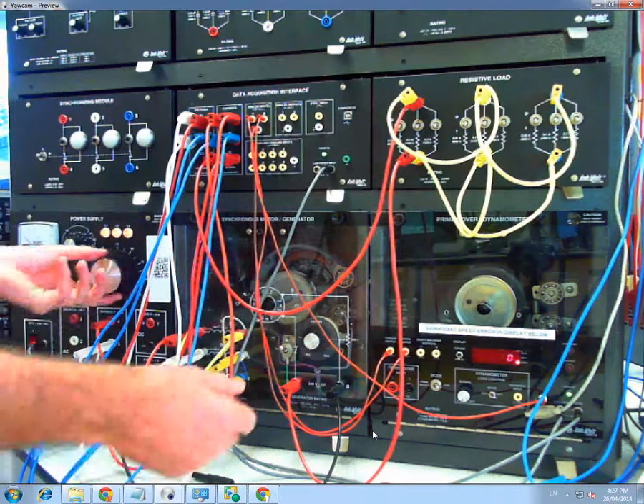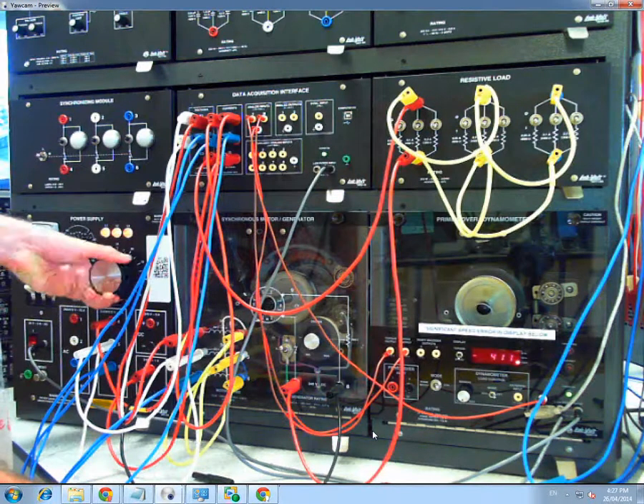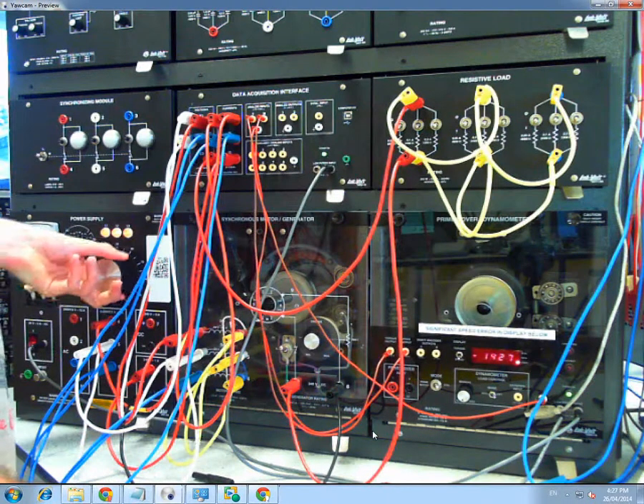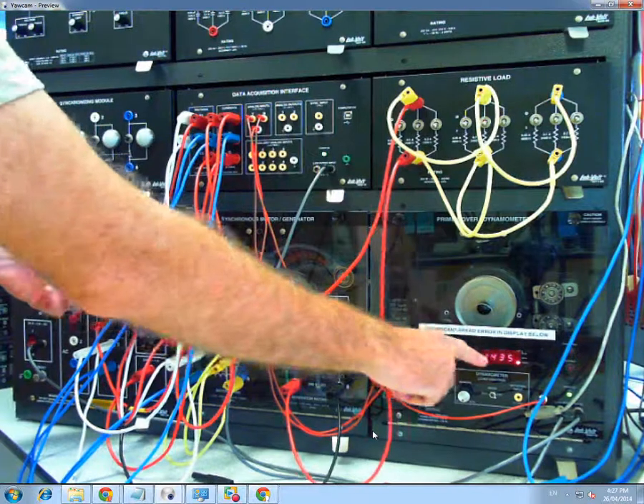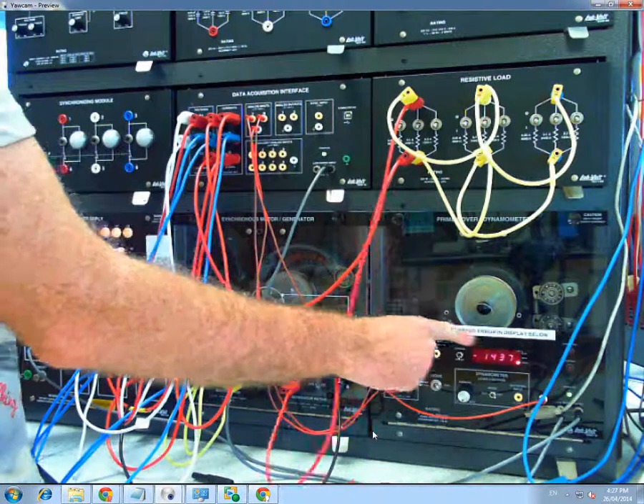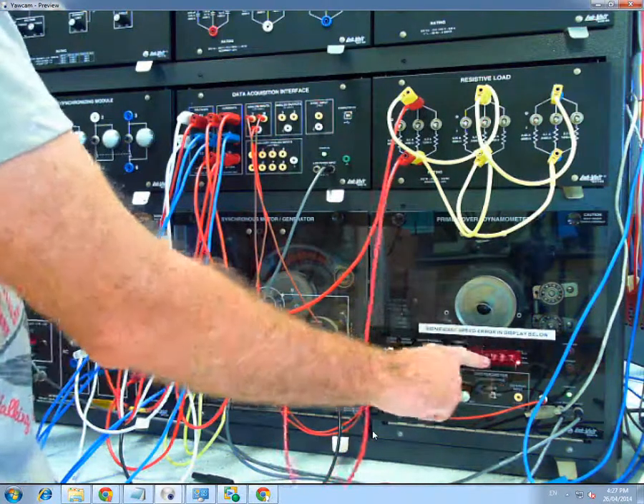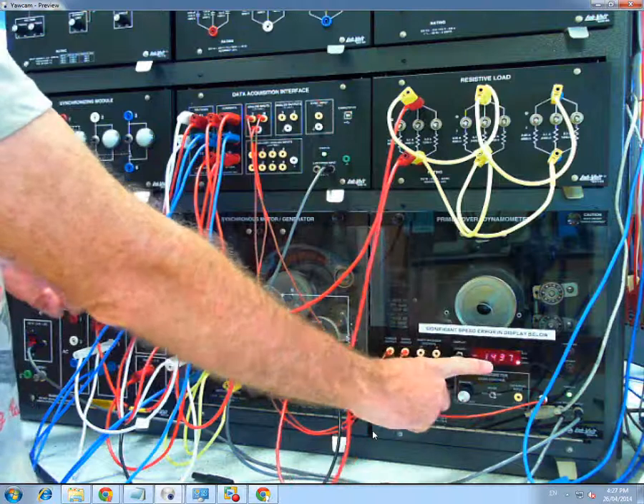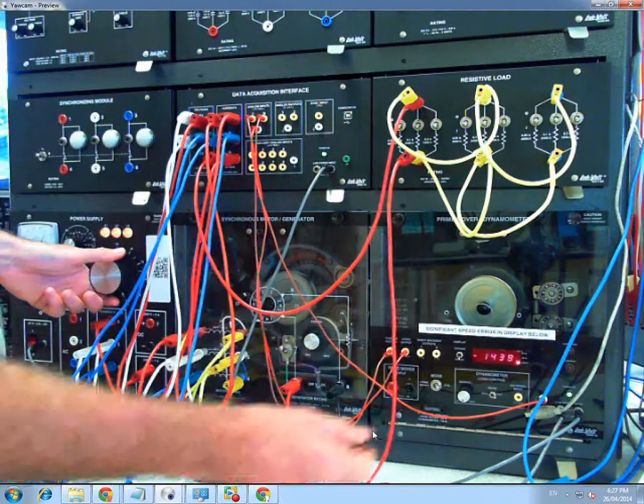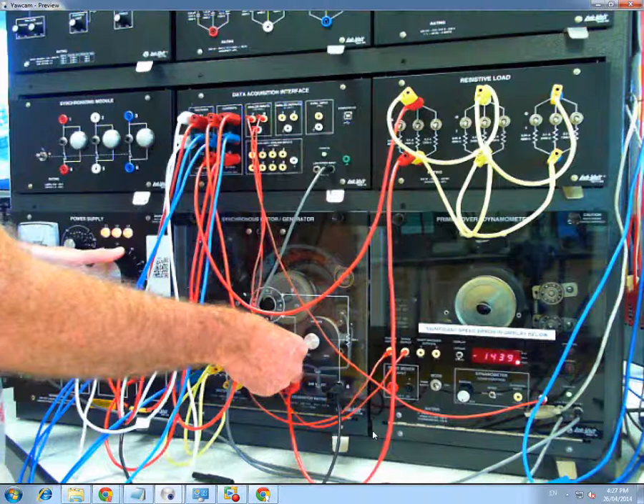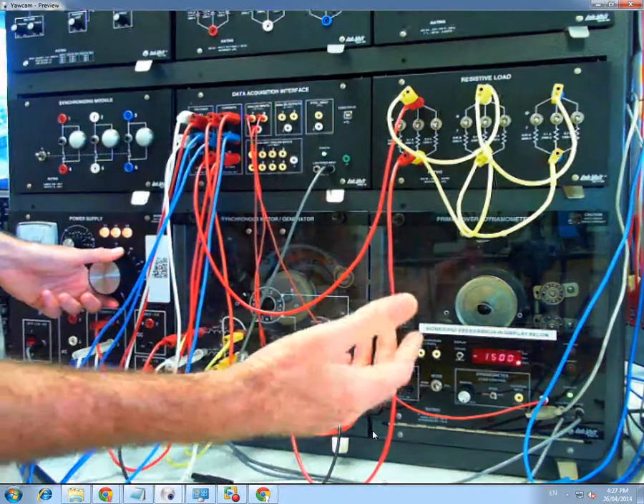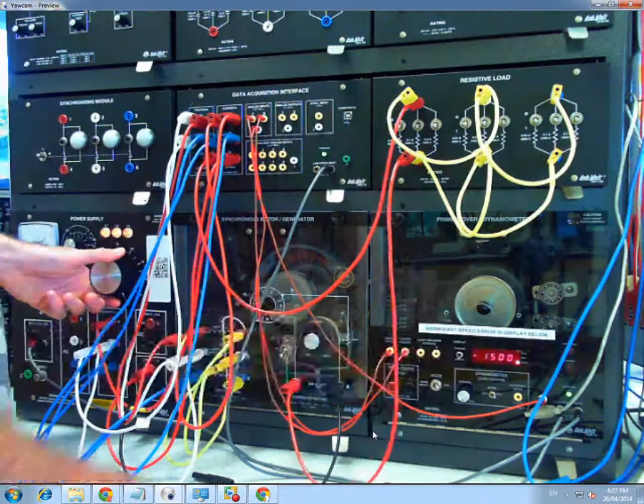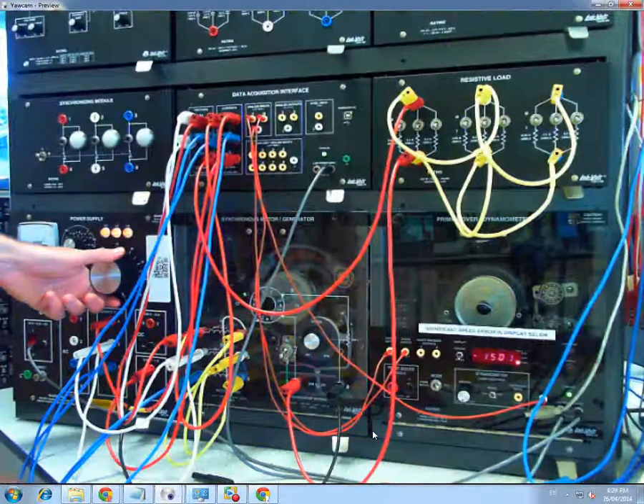So, I'll just demonstrate that. So, I think when it's close to synchronous speed, this actually is fairly correct. It's only at lower speeds it's out. So, basically this is showing 1437 RPM. And now when I throw the excitation on, you can hear it jump up to speed. And now it's locked in sync at 1500 RPM.